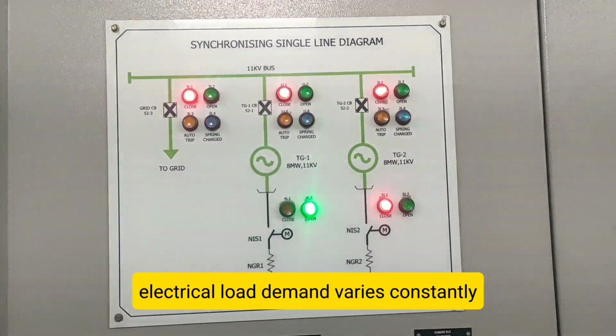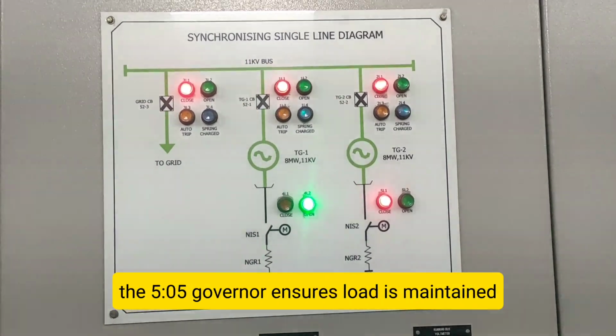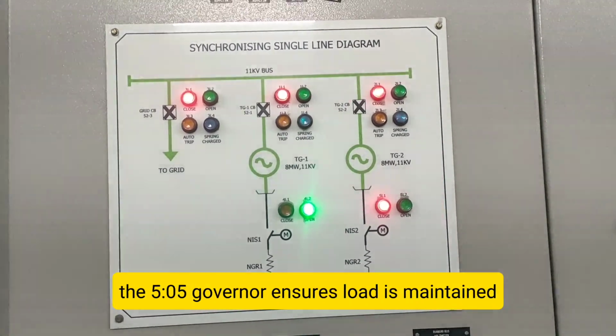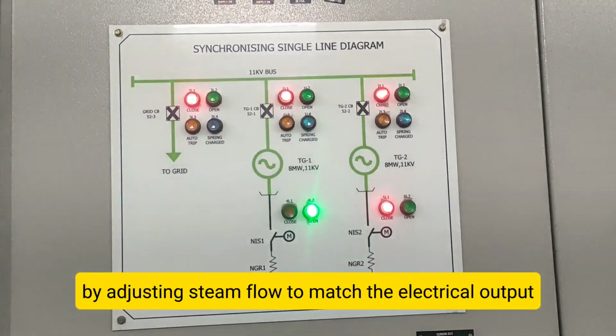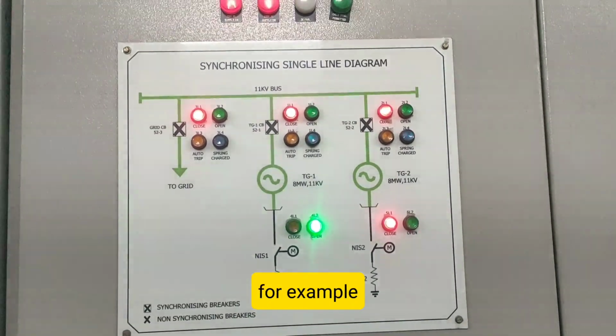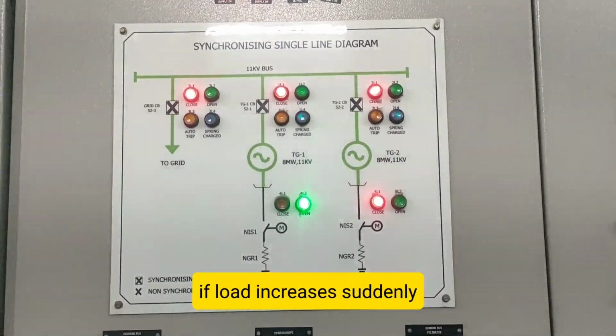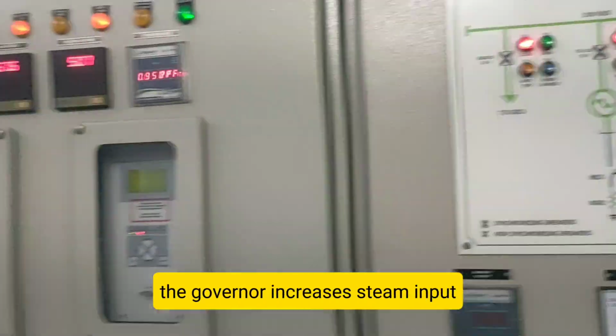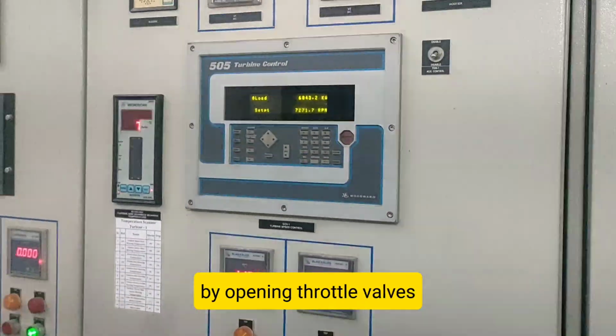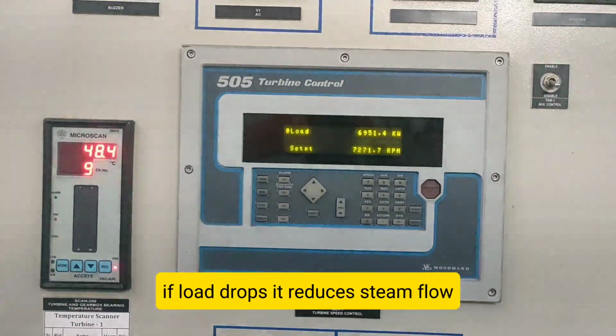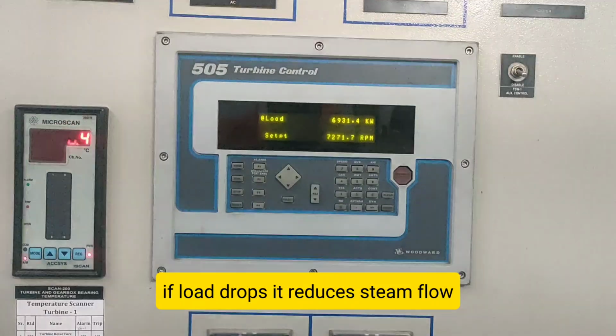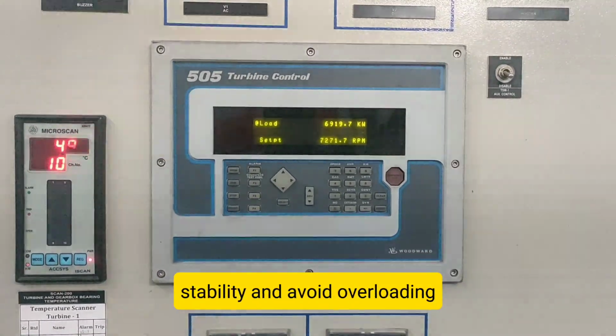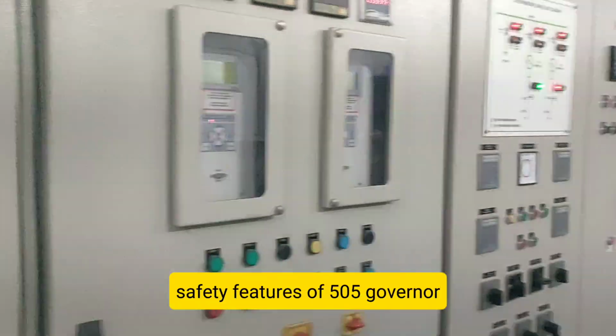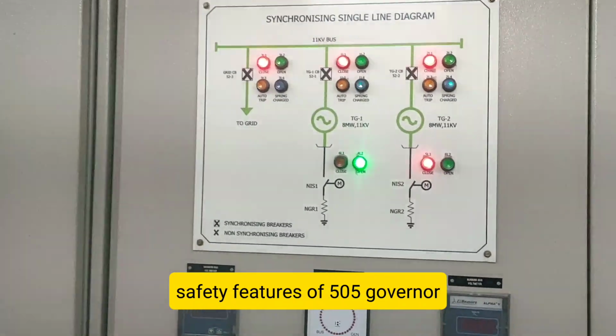The 505 Governor compares actual RPM with the set point, e.g., 3000 RPM for a 50 Hz system. If RPM drops, load increases, the Governor opens throttle valves more to increase steam flow. If RPM rises, load decreases, the valves are closed slightly to reduce steam input. This regulation happens many times per second to ensure precise control.